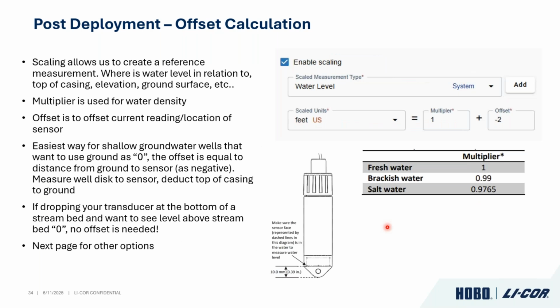So this is going to be a couple of slides talking about this, because it's a little different than how we do it with some of our other equipment in utilizing reference levels. But what we use in this case, because it's already taking a water level measurement the minute you drop that transducer in, is what's called an offset. It's really to offset what it's reading and get it to a reference point that makes sense to you. One of the things you'll see here when you click on enable scaling, typically I do water level, scaled units feet, and then your multiplier right here really is in relation to freshwater, brackish or salt. So it's a different density essentially. So these are the multipliers you should use for that, which can all be seen in the manual or quick start guide. Now an offset, again, is going to get us to a desired reference point essentially.